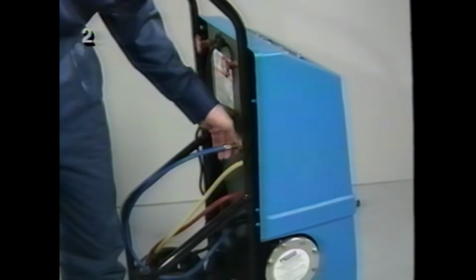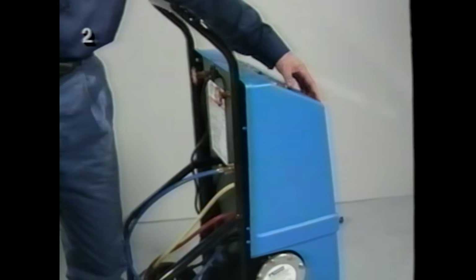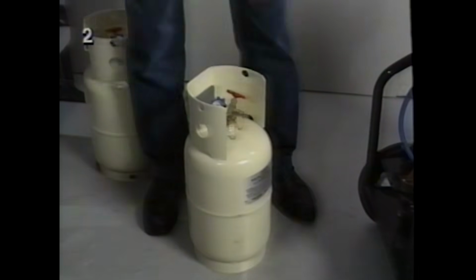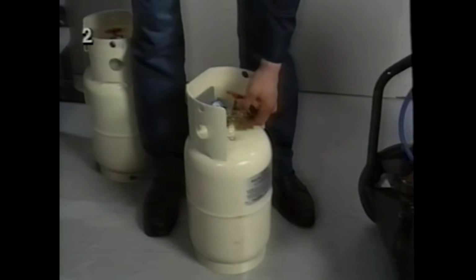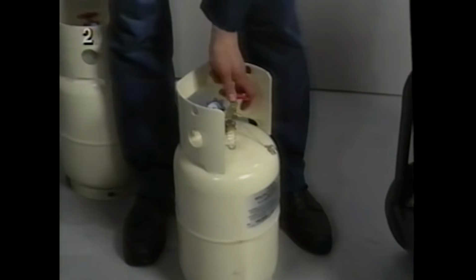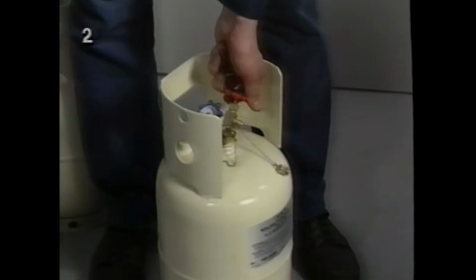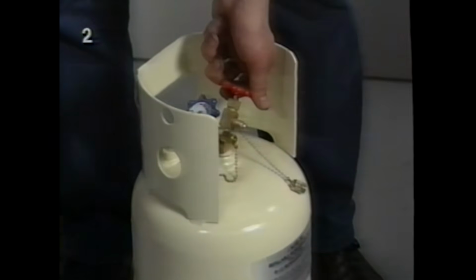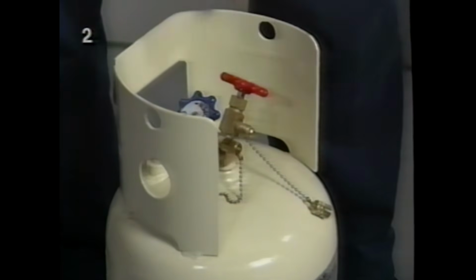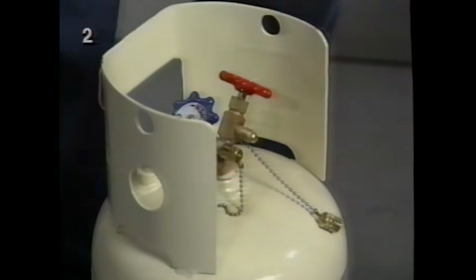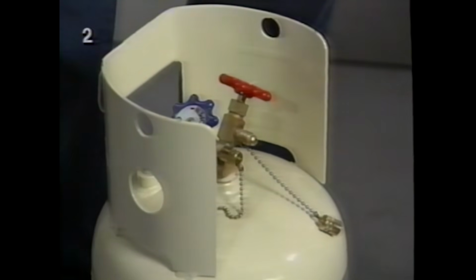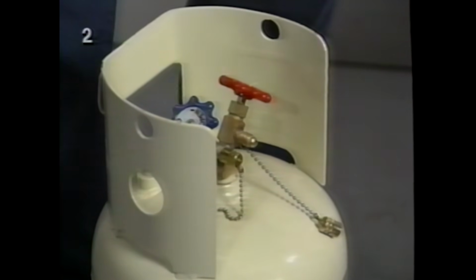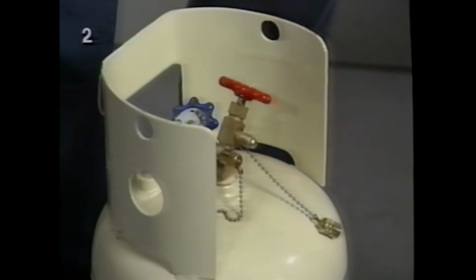The blue hose goes on the vacuum pump next. You should run the pump for 10 minutes to get all the air out of the filter. Then turn the pump off and take off the hose. Before you attach the recovery tank to the ACR3, remove the sealing cap and open one of the valves. This bleeds off dry nitrogen under pressure used to keep the tank clean for shipment. Don't use any new tank that doesn't have the seal or doesn't hiss when you open the valve.